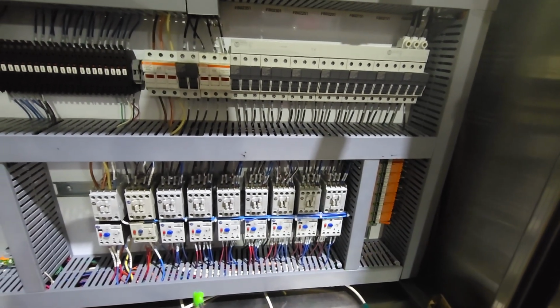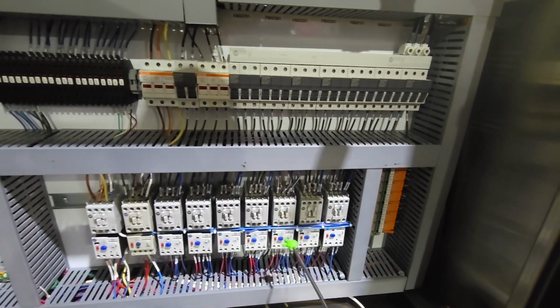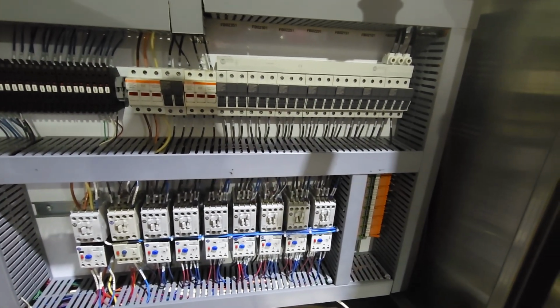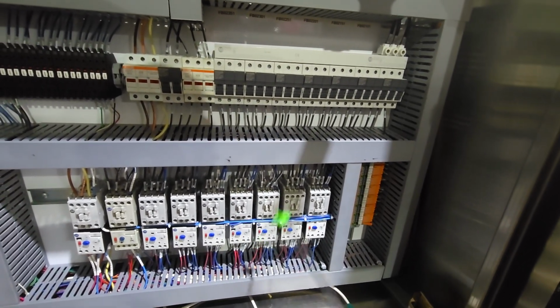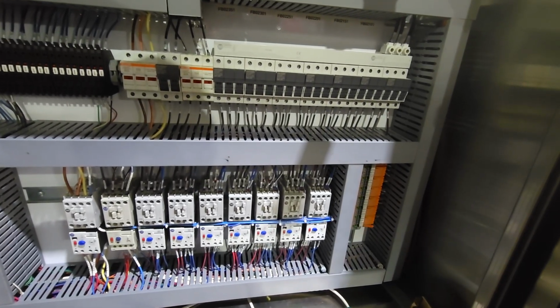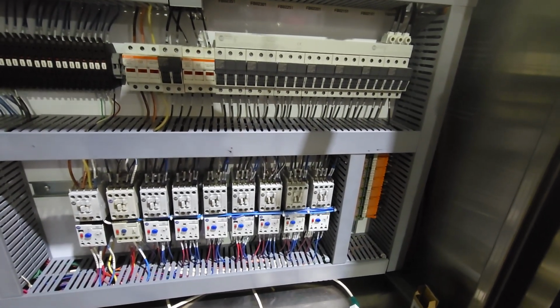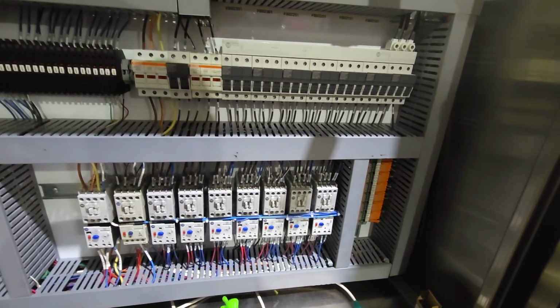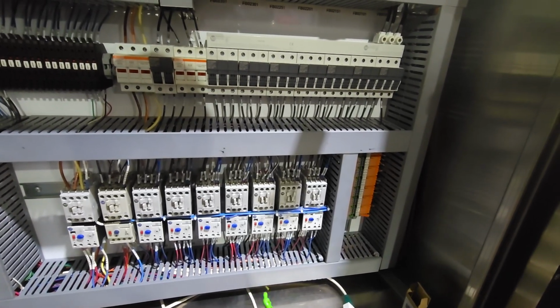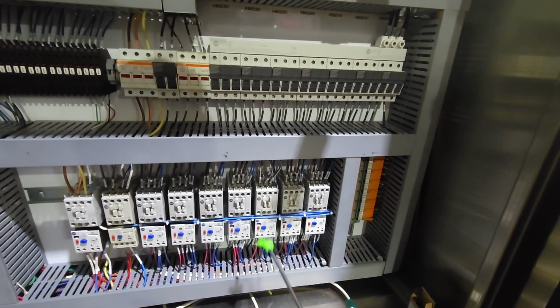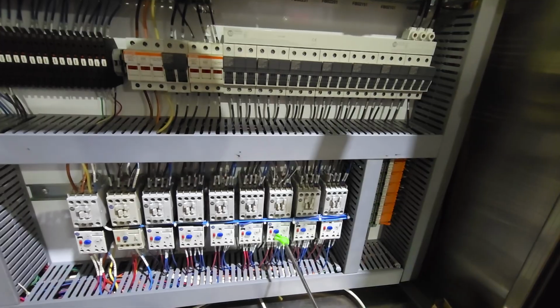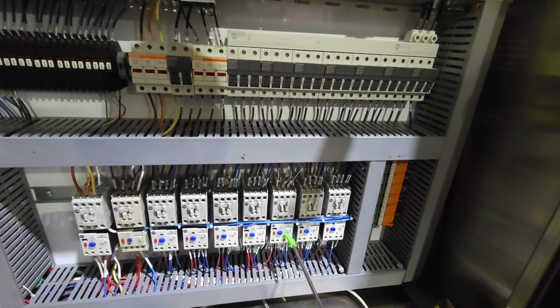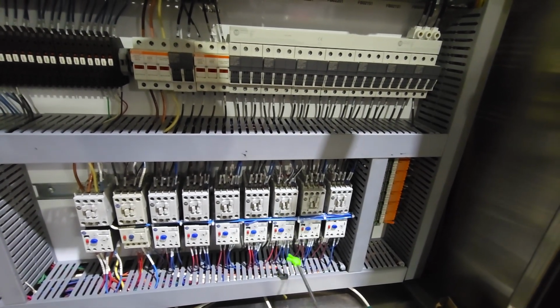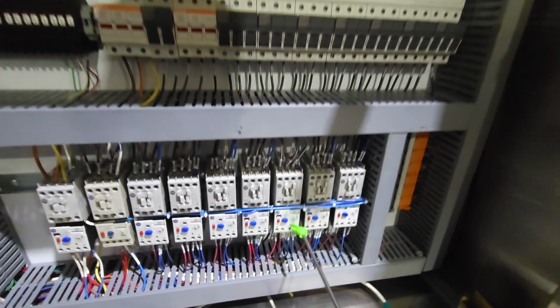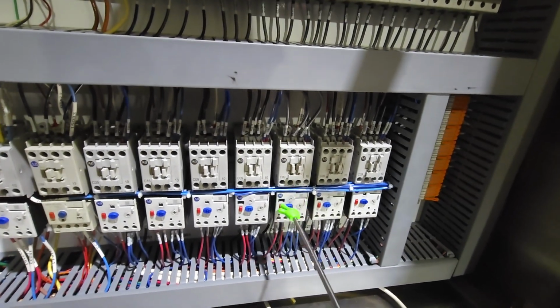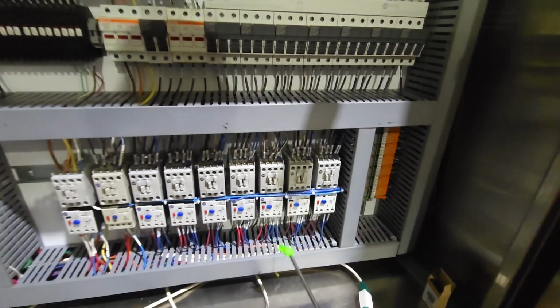You will run into other issues, like for instance, if you keep getting a fuse blown and it blows again immediately, your pump might just be bad, or it could be a few things, but most likely your pump's just bad. Usually it don't happen. Now you might get multiple overloads. Well, we can adjust how high the overload's set and we can multiply it. It looks like this one's set pretty high. They got this one set at 30 amp and it looks like it's multiplied by 4.